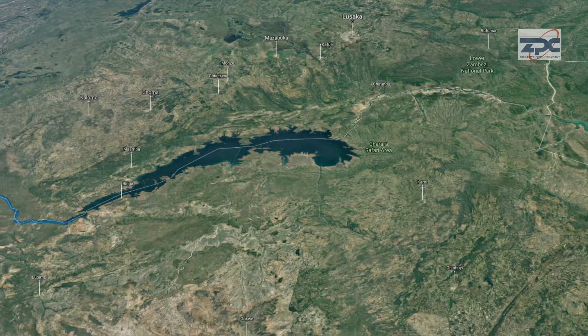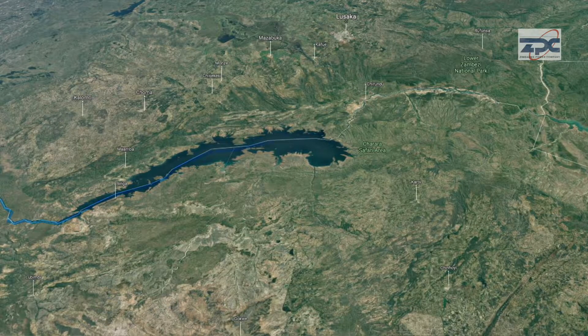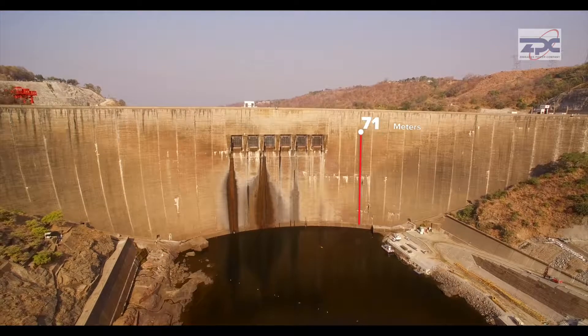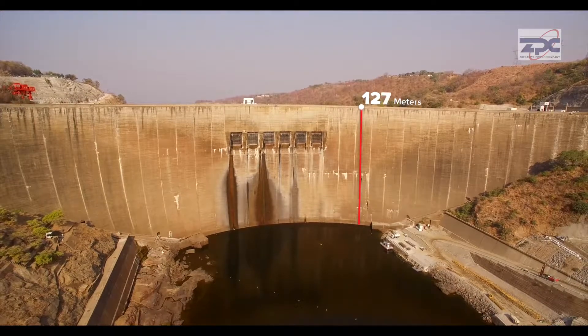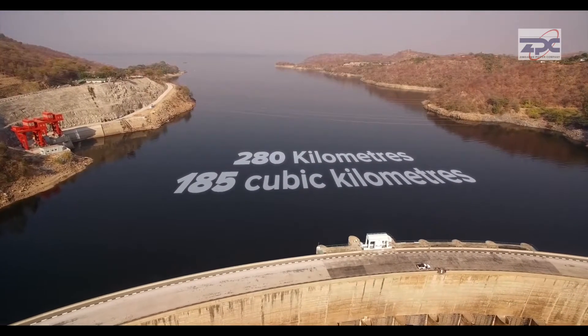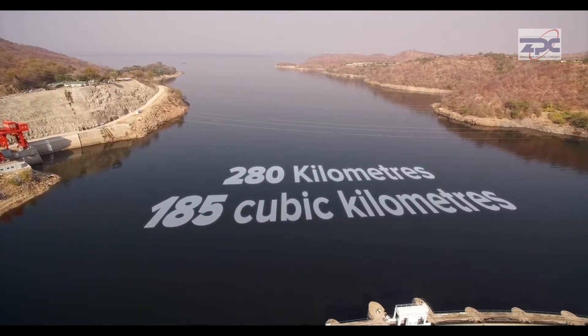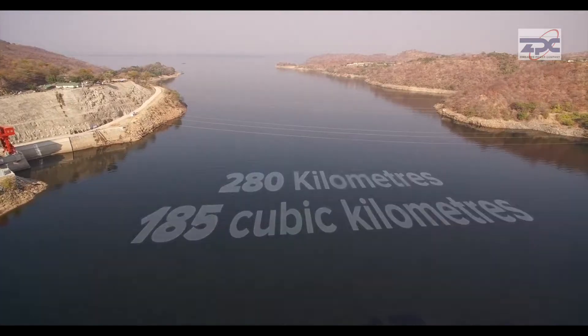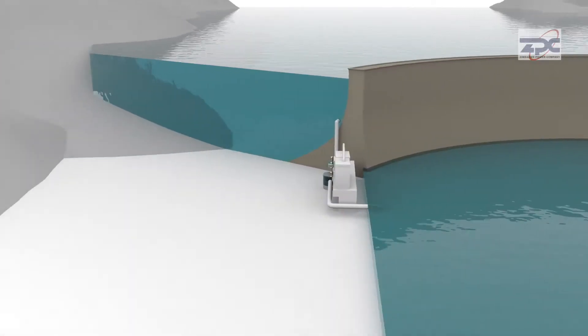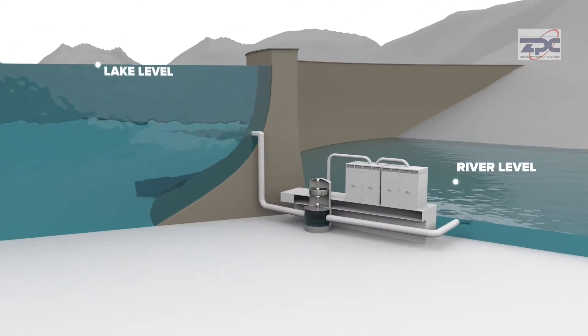Along the way, the power of the river has been harnessed at two points: the Kariba Dam and the Cahora Bassa Dam. The Kariba Dam stands at 127 meters tall and 579 meters long and forms Lake Kariba, which extends to 280 kilometers with 185 cubic kilometers of water. The Kariba Dam is used to create a water head, which is essentially a height difference between the lake level and the river level.